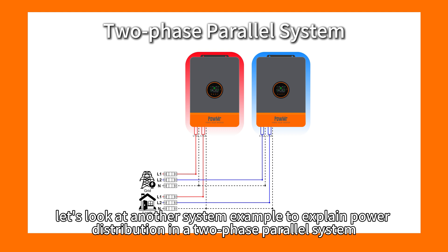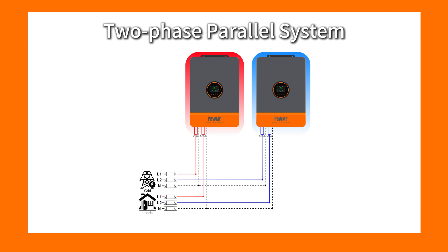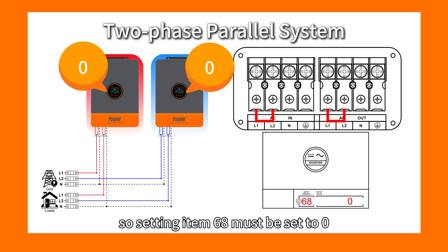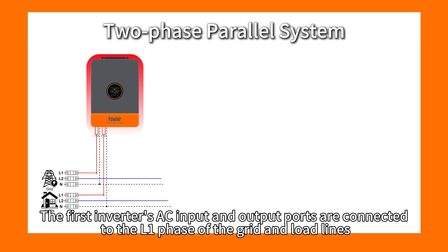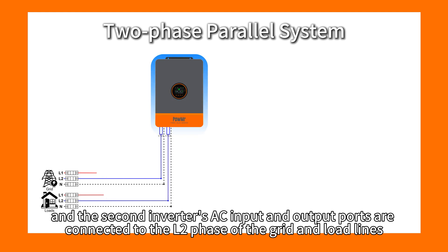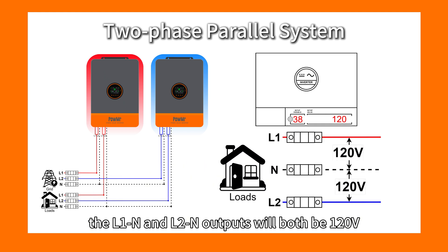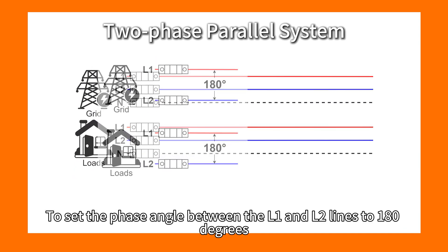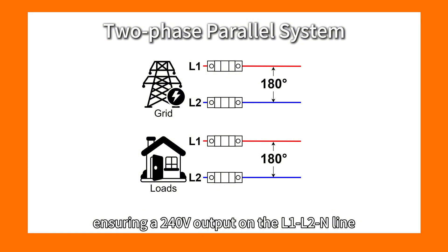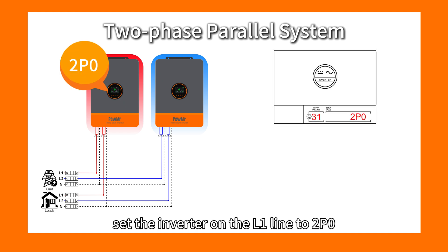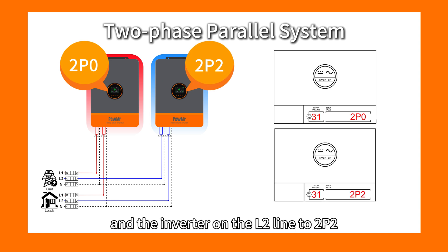Next, let's look at power distribution in a two-phase parallel system. In a two-phase parallel system with two inverters, the L1 and L2 AC ports are connected in parallel, so setting item 68 must be set to 0. The first inverter's AC ports are connected to the L1 phase, and the second to the L2 phase. Assuming setting item 38 configures the output voltage to 120V, the L1-N and L2-N outputs will both be 120V, with a 180-degree phase angle between them ensuring a 240V output on the L1-L2-N line. Setting item 31 should be set to 2P0 for the inverter on L1 and 2P2 for the inverter on L2.